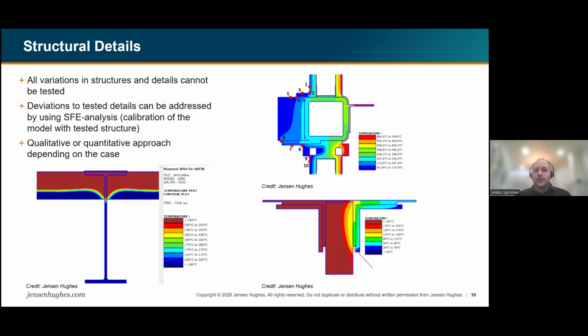And if it doesn't work, we can propose some more protection, for example. These examples here are related to compartmentation. For example, the one on the left, where we have a steel beam inside a concrete slab partly. There was a question about how much the steel conducts heat to the upper—sorry, in this one, the fire is on the top floor—so how much the steel conducts heat to the lower compartment, and we could conclude that it's within the limits of the acceptance criteria in this case.